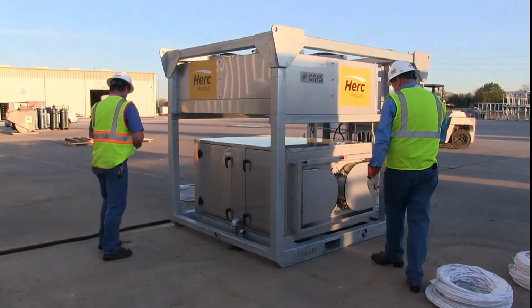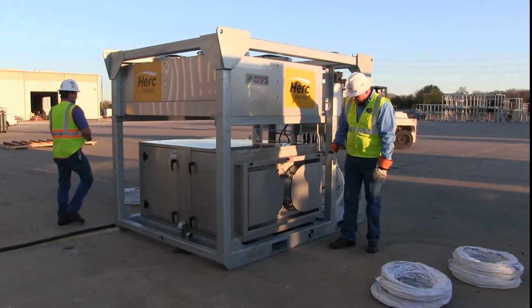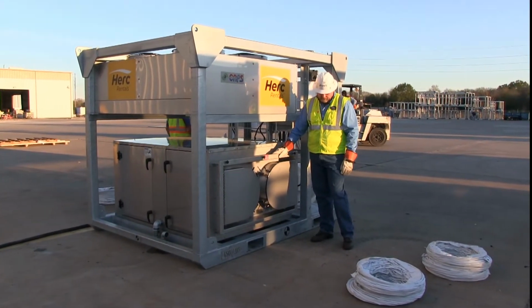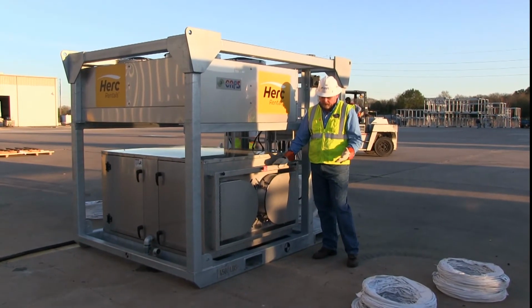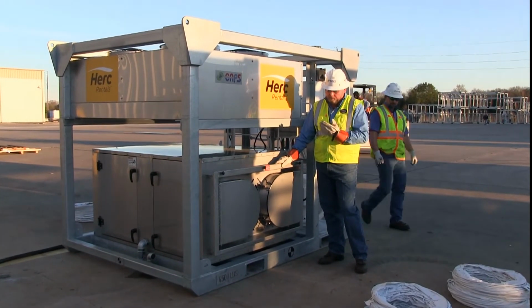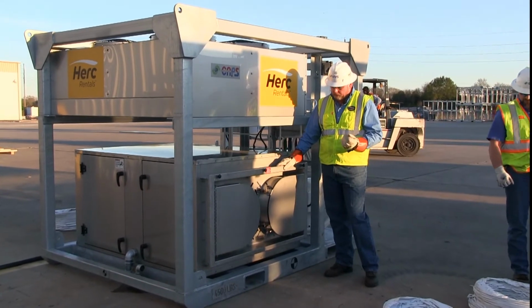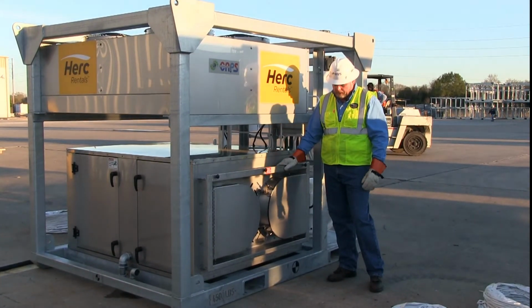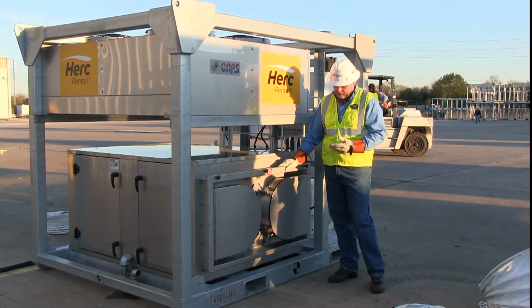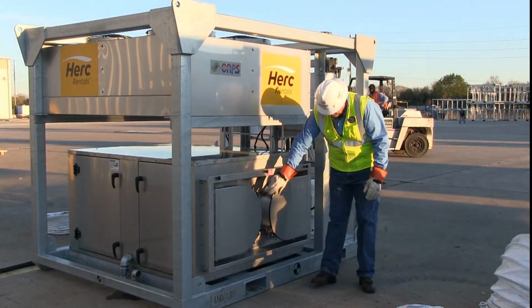Next step is going to be to hook up the ductwork on our CAPS. This is a 100% outside air unit. It's designed to take in 95-degree air and in one pass drop 40 degrees, which will produce 55-degree air. It can be either free inlet or ducted. We're going to demonstrate the ducted.